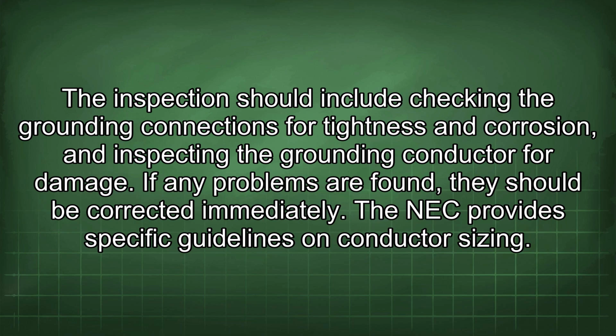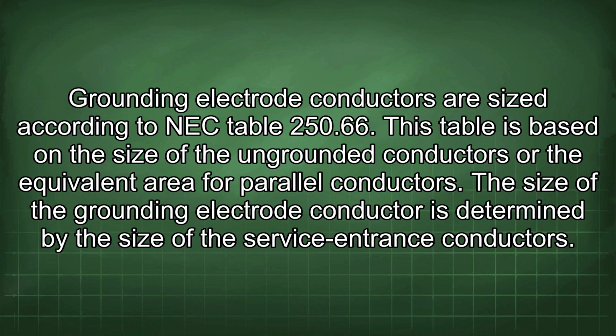The NEC provides specific guidelines on conductor sizing. Grounding electrode conductors are sized according to NEC Table 250.66. This table is based on the size of the ungrounded conductors or the equivalent area for parallel conductors. The size of the grounding electrode conductor is determined by the size of the service entrance conductors.